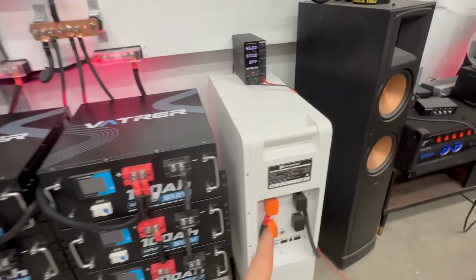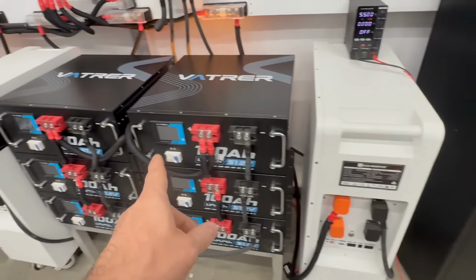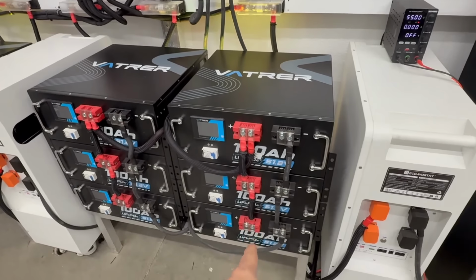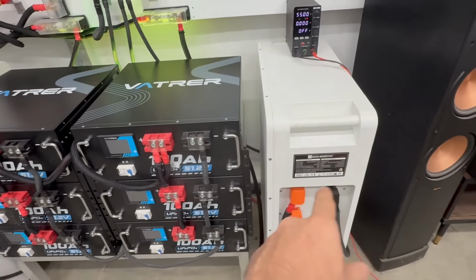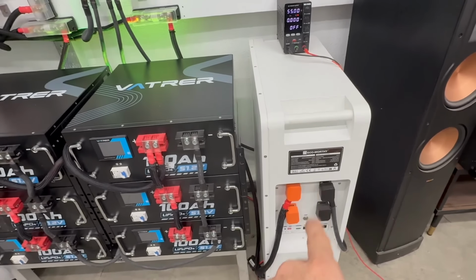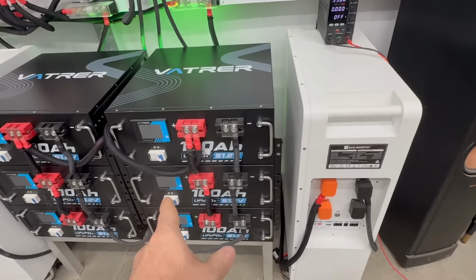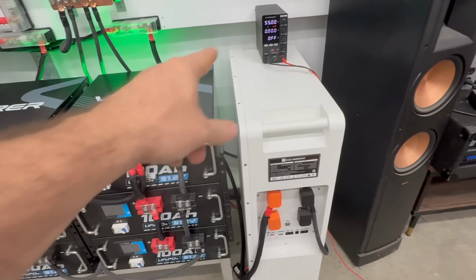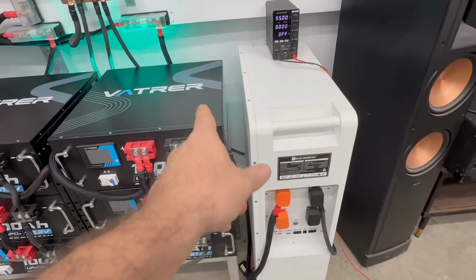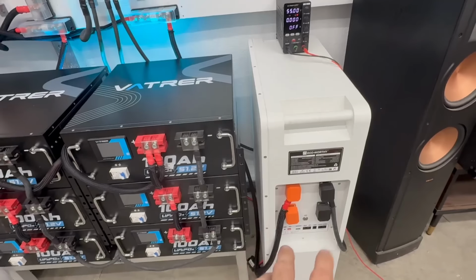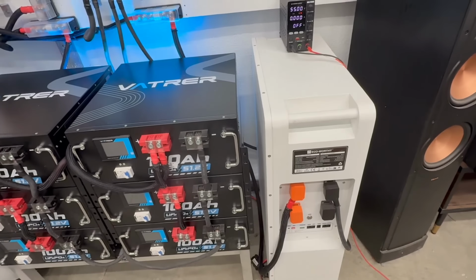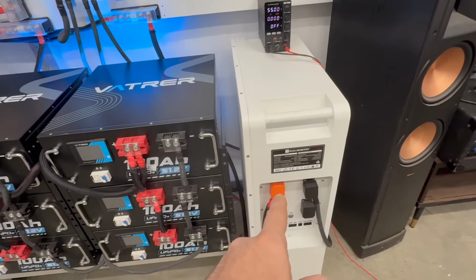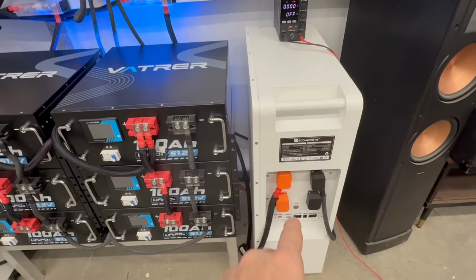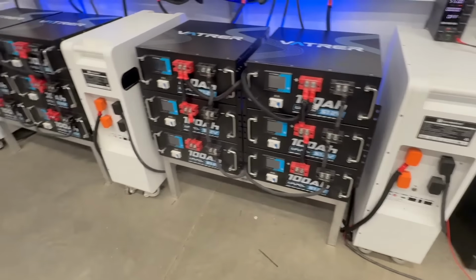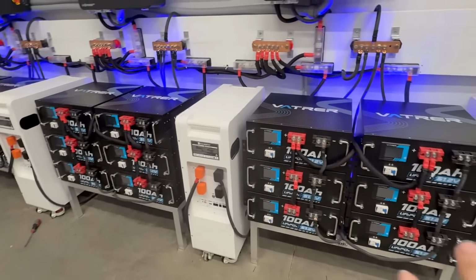When I say balanced, if you look at these eco-worthy batteries, which are 280 amp hours, and you have essentially one big battery that's 300 amp hours, your 280 amp hour battery should charge and discharge faster than the others because they're different sizes. So on this one I did add an extra foot of positive and negative to compensate. If it's not needed after charging and discharging a bunch of times, and this one seems lazy compared to the others, I'll shorten it up to match. But I wanted to try to do whatever I could to balance everything.